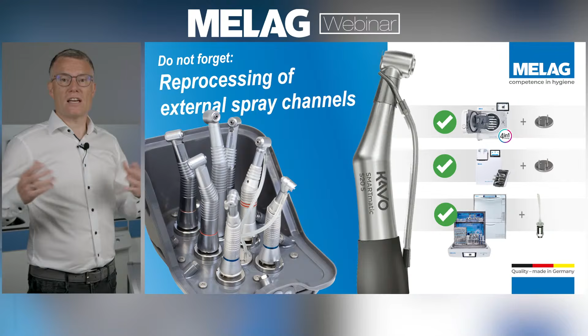Right. Another very important part, when we're talking about the shape or the use of a dental rotating handpiece, is that we do have dental handpieces that might be used for surgical treatments, and they are manufactured to be a special surgical handpiece, and they might have an external cooling channel, and this external cooling channel is defined as a hollow body. So we need to take care of that as well. So we need to have some kind of specific adapter, and we have here a wonderful slide where we can see that for several solutions, such as CareClave, such as MELAG, such as the Melatherm 10 Evolution or Melatherm 20 units, we do have a corresponding adapter that is taking care of those external spray channels as well.